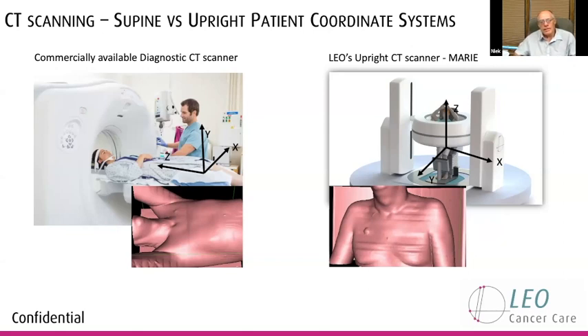A great example is something people always love to see. They're using their robotic positioner to go fetch the CT daily QA device, and the positioner just puts the daily QA device right into their CT scanner. So then they can check the accuracy of the positioner and the CT scan. So there's a huge amount of benefits that are going to come out of that. In fact, that's probably a talk on its own, the efficiency we're going to see around just the normal daily, monthly, annual QA of such a system.